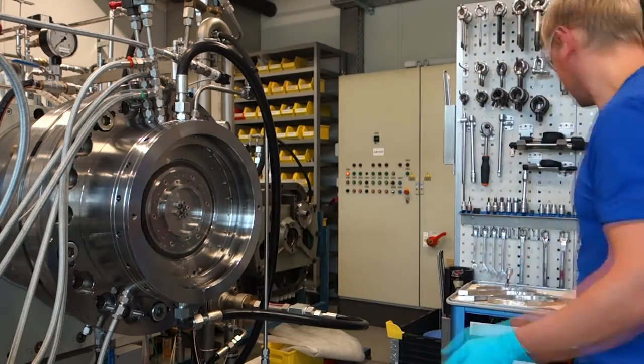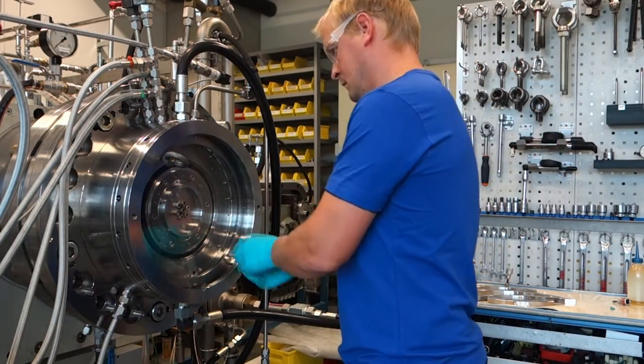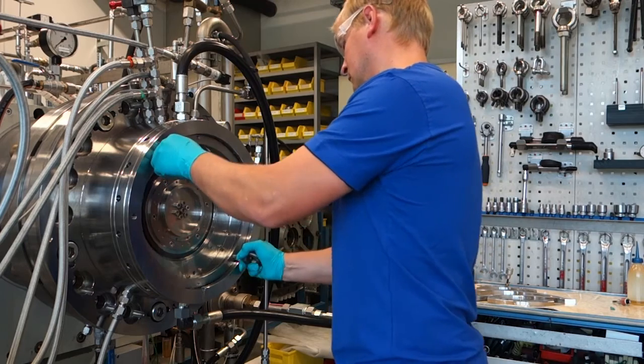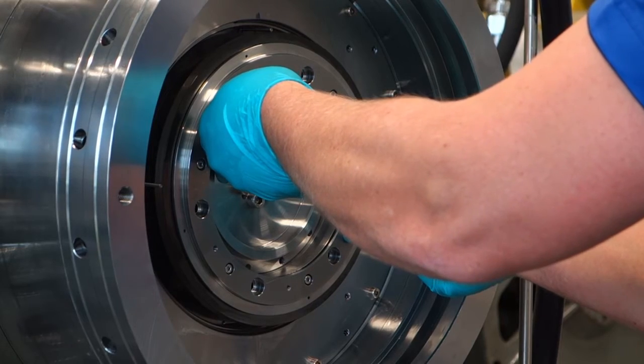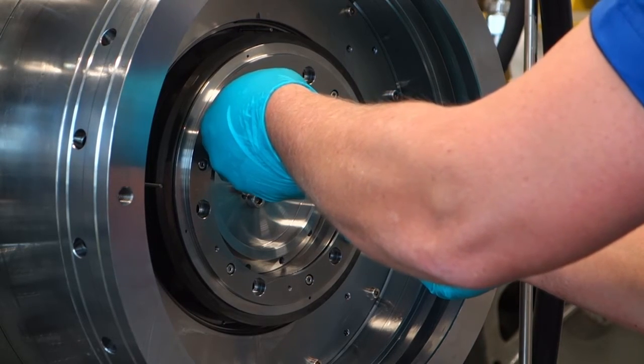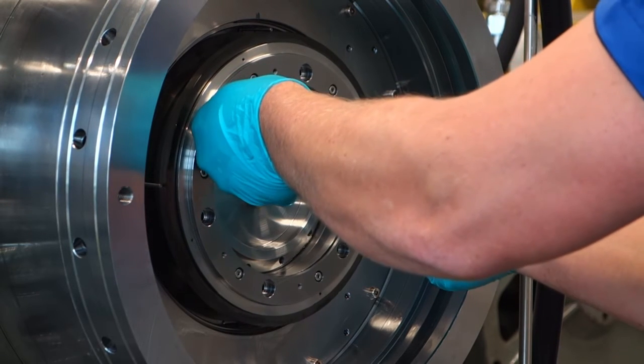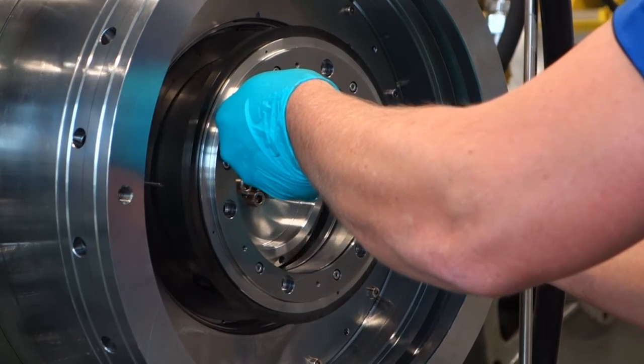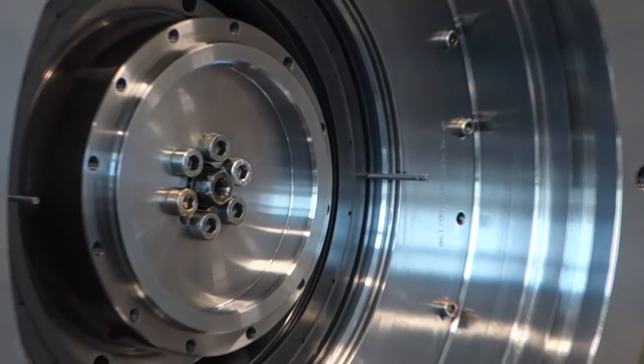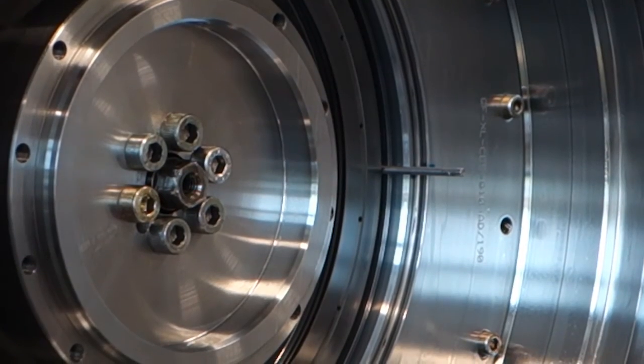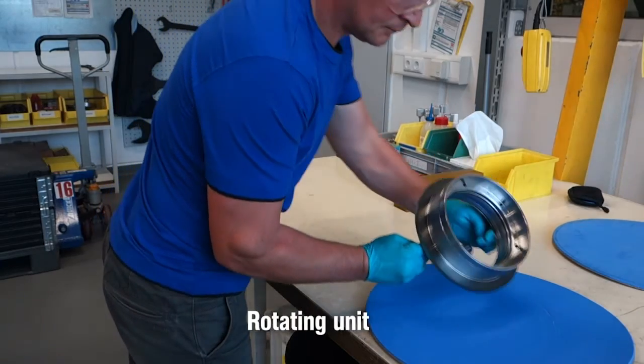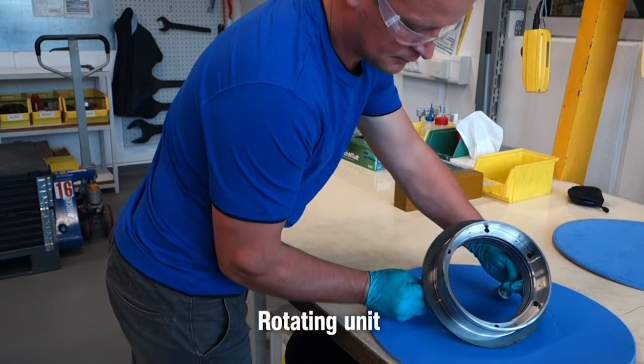The COBA seal is then removed, dismantled, and inspected in order to assess the condition of the seal after the test. The rotating unit is dismantled with care. The seal face of the rotating unit shows no contamination whatsoever. No oil has penetrated between the faces during standstill.